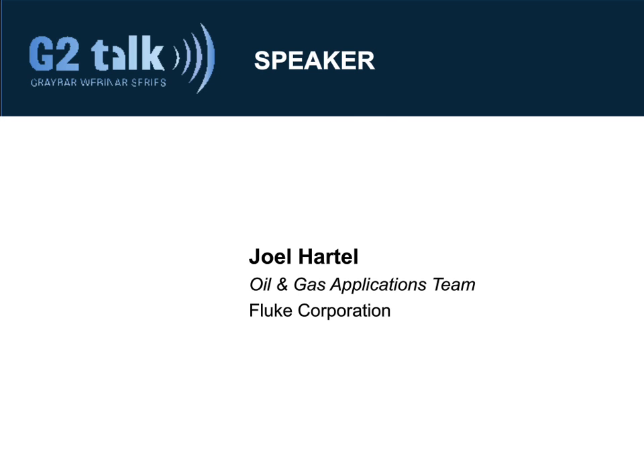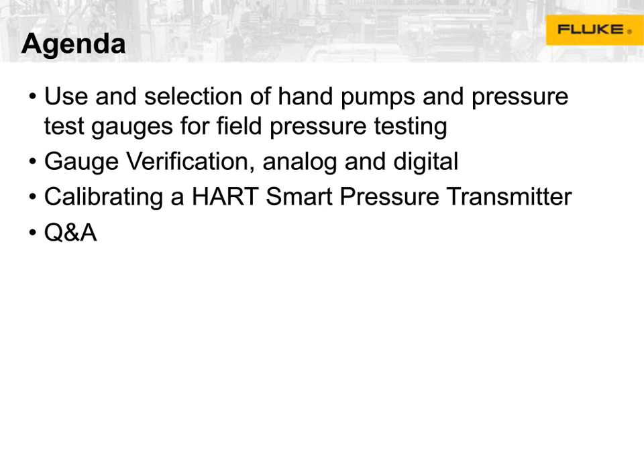So we're going to talk about 3 applications today and then have a Q&A session. The 3 applications were sent out as part of the meeting notice, and they are use and selection of hand pumps and pressure test gauges, field gauge verification for both analog and digital gauges, and then last but not least, calibrating a HART pressure transmitter. After that, we're going to have a short Q&A.